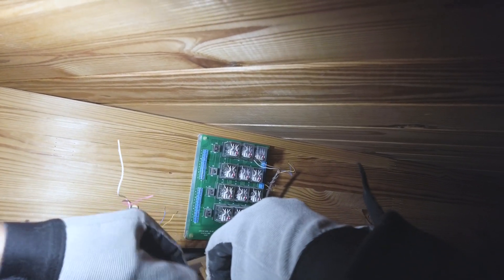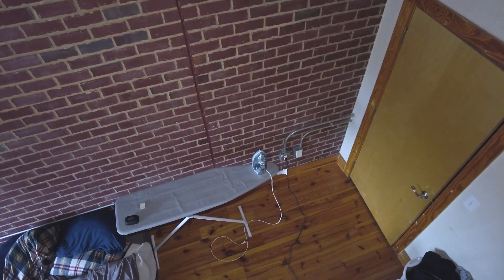The installer ran conduit behind the plenum — well, back behind the plenum on the package unit — and it was within inches of the heat strips. So that basically melted the wire into just one big wire. The outside was still intact, but it fused two thermostat wires together and they were just all solid, one wire. So there was a pretty bad short there.